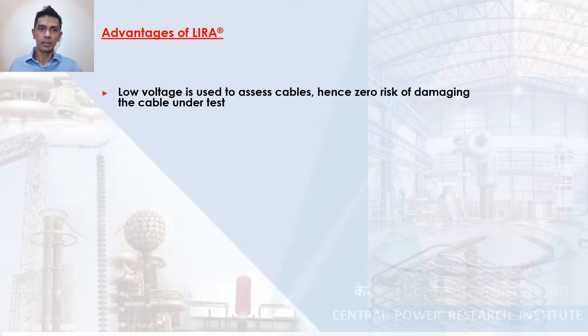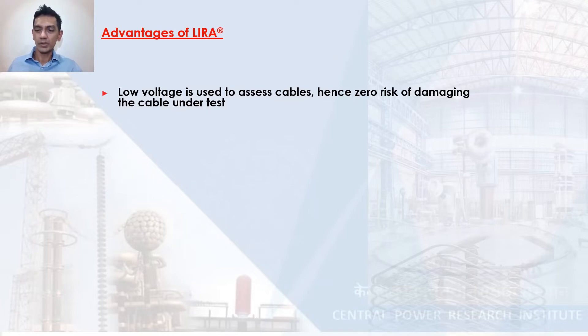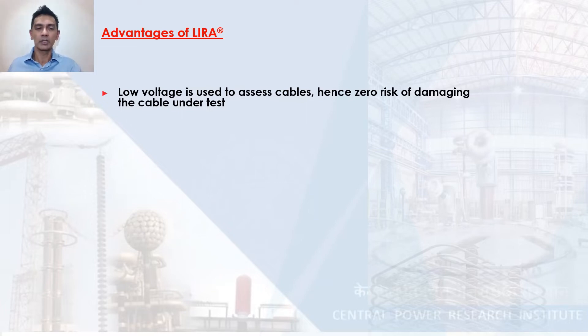What are the advantages of Lira? The first advantage is that we use low voltage to assess the cable health. Hence there is no risk of damaging a cable while doing the testing, which is something that is always a concern when you are doing high voltage testing such as standard partial discharge.